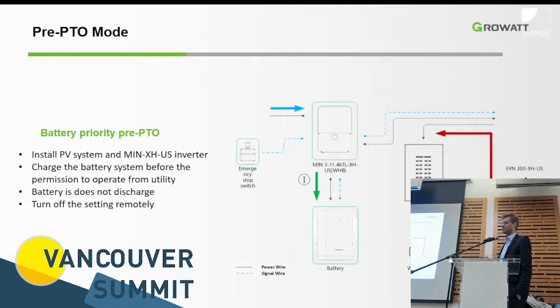This is a cool feature, not necessarily for the Canadian market, but in the US it's super popular. In the US, solar installers install a system, and it typically takes quite a long time until the utility company gives the final okay to be grid interactive, so to feed into the grid. At that point, you can give the installer a pre-PTO mode, which means that you do the self-consumption and zero feed-in. So the customer still has all the benefit for the self-consumed energy being produced by the solar on the roof with the battery to assist, but they're not feeding into the grid until the utility company says, now we are ready, and here's the paperwork that you're officially allowed to connect to the grid.